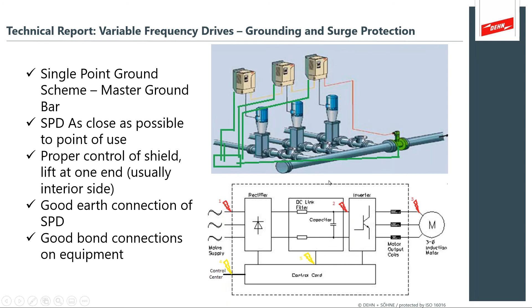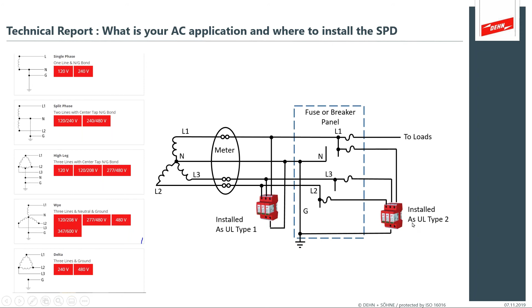Are there SPDs on the emergency safety interlocks, on the emergency light systems, on coaxial radio antennas, direct connection to earth? These are the things we're looking for, and that should be part of your findings. Then there's the selection of proper surge protection devices based on the electrical apparatus in front of the fuse panels, directly at the point of use. It's really important that the electrical panels are properly protected.